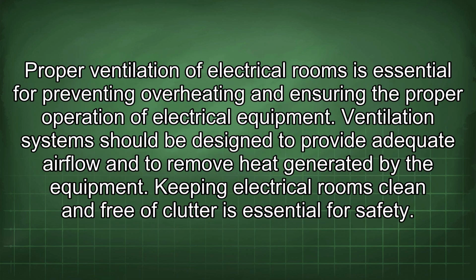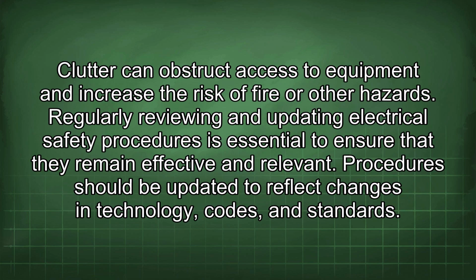Proper ventilation of electrical rooms is essential for preventing overheating and ensuring the proper operation of electrical equipment. Ventilation systems should be designed to provide adequate airflow and to remove heat generated by the equipment. Keeping electrical rooms clean and free of clutter is essential for safety. Clutter can obstruct access to equipment and increase the risk of fire or other hazards. Regularly reviewing and updating electrical safety procedures is essential to ensure that they remain effective and relevant. Procedures should be updated to reflect changes in technology, codes, and standards.